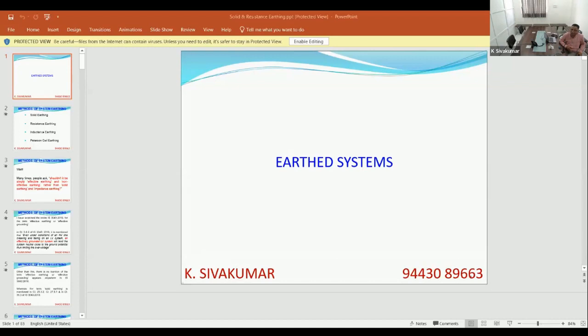If the resistance is very low, the system is effectively earthed. Definitely, the standard says that R0 by X1 has to be less than 1. You know your system positive sequence impedance.